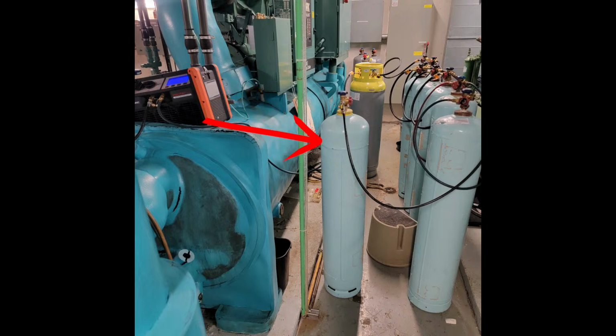One question that comes up is, why didn't you use a big 1,000-pound cylinder? Well, in this particular case, this machine had gone almost flat. We got about 200 pounds out of what's supposed to be 1,500 pounds in the chiller at the time. This is what the refrigerant supplier could ship us. They sent all these blue cylinders on a pallet, and we rolled them into the plant and began charging. The cylinder we were using at the time was a 240-pound one, and these others are 125s, so this is what we put the little bit of leftover refrigerant into.